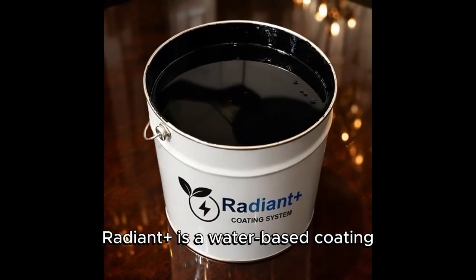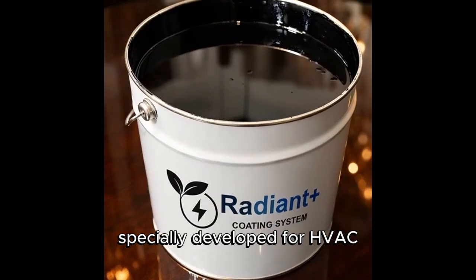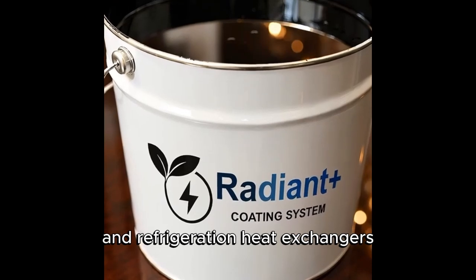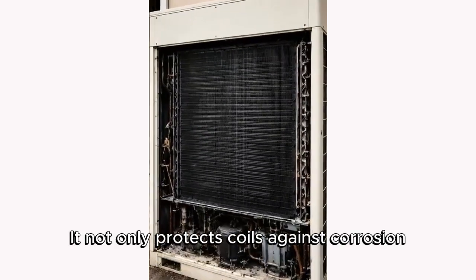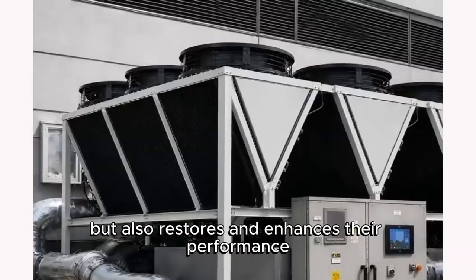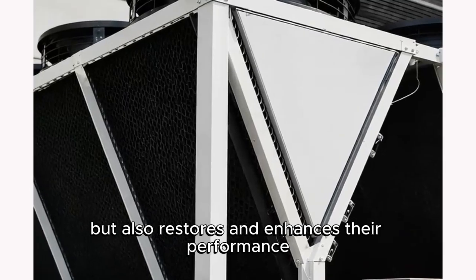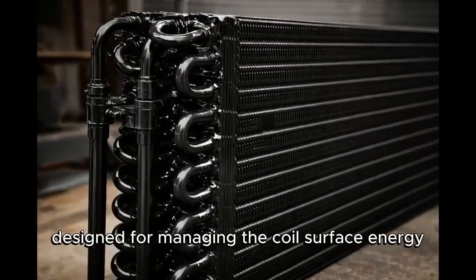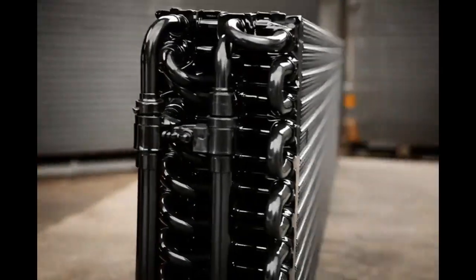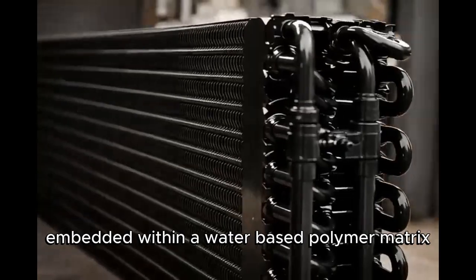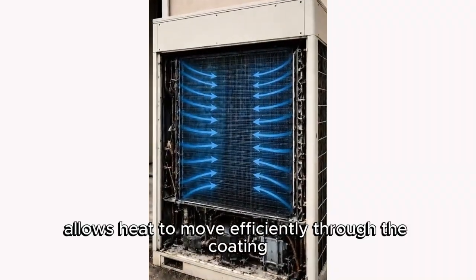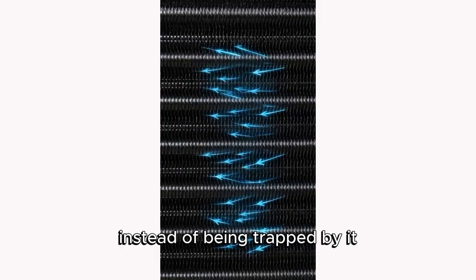Radiant Plus is a water-based coating specially developed for HVAC and refrigeration heat exchangers. It not only protects coils against corrosion, but also restores and enhances their performance. The coating contains particles designed for managing the coil surface energy, embedded within a water-based polymer matrix, which allows heat to move efficiently through the coating instead of being trapped by it.